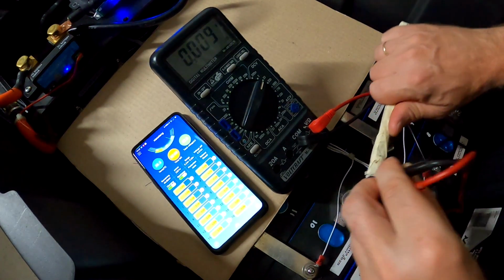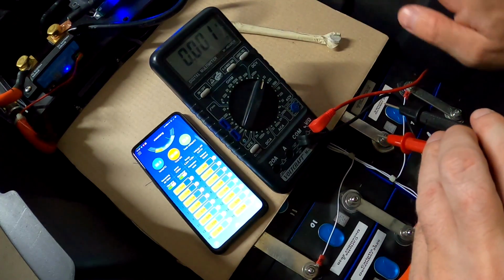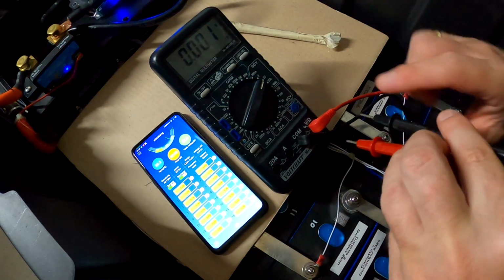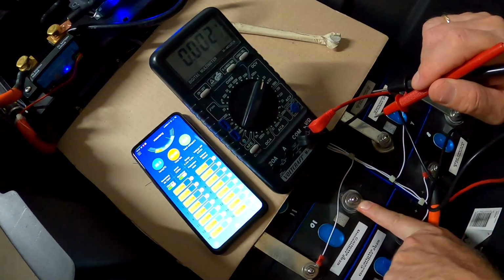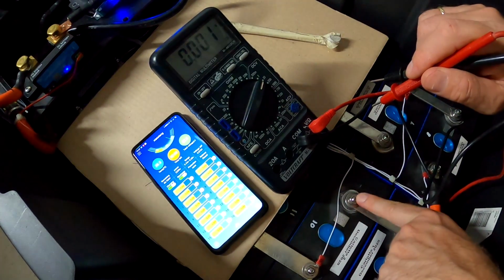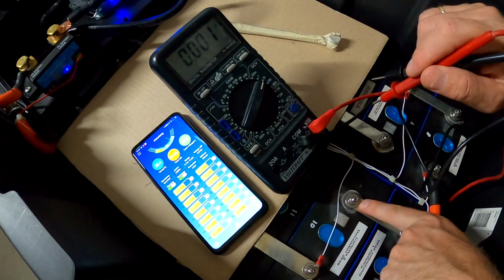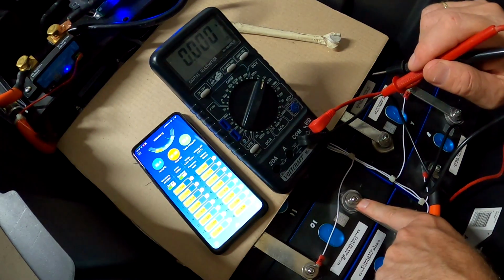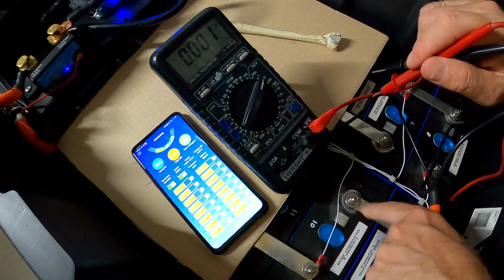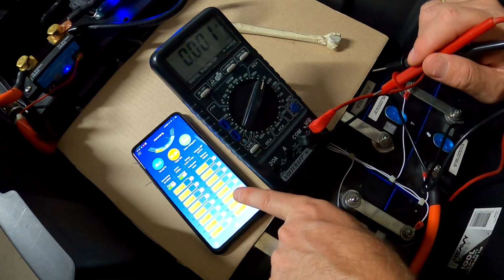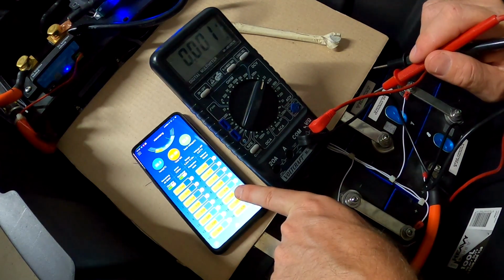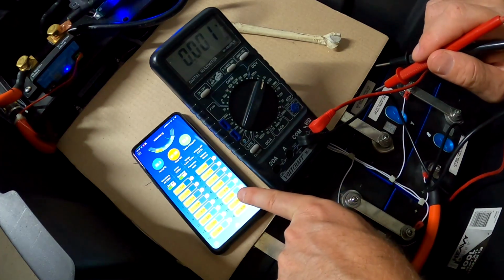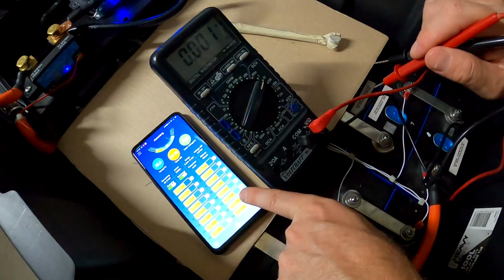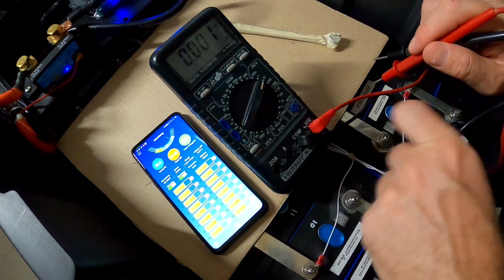I have done this with another cell, and it was 1 millivolt afterwards. I cannot do it with number 10 though. Something is not right with the bus bar or the actual terminal here, so I have to take this apart again and change it. But you can see it has actually made a difference of about 10-15 millivolt already in the BMS, so it's not flagged as the lowest cell anymore.